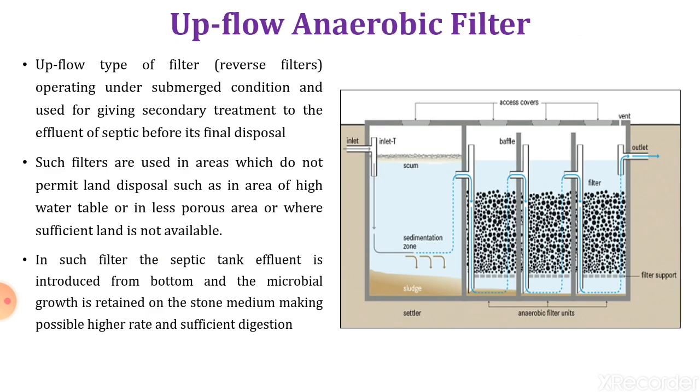Upflow anaerobic filter. An upflow type of filter, that is a reverse filter, operated under submerged condition and used for giving secondary treatment to the effluent of septic tank before its final disposal. Such filters are used in areas which do not permit a land disposal, such as areas of high water table or less porous area, or where sufficient land is not available.